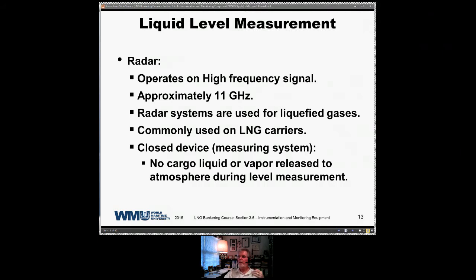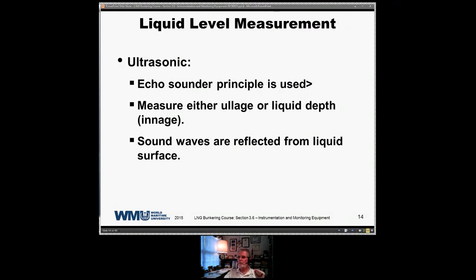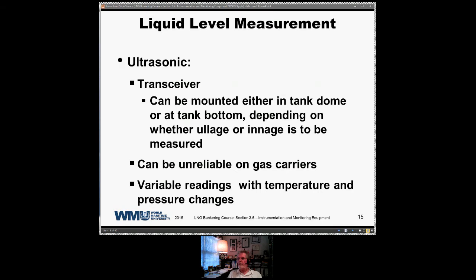so you always know instantaneously what the level of the tank is at all times. Ultrasonic uses the echo sounder principle. You're using a reflected sound wave, and you can calculate the ullage, which is the void space in the tank where there is no cargo, or you can actually measure the depth of the liquid, the innage of the tank, and this is all done by determining where you're going to locate your receiver. Sound waves are reflected from the liquid surface. With ultrasonic, you have a transceiver, which can be mounted either in the tank dome or at the tank bottom, depending on whether you're going to measure ullage or innage. It makes very little difference because from either one you can calculate the amount of cargo.